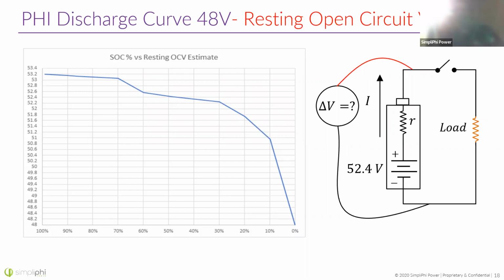This is the voltage that the battery would read if it was not powering loads, an open circuit condition. I want to make clear that the voltage of the battery bank depends on two things: state of charge, and to a small degree temperature, but mostly state of charge, as well as internal voltage drop due to internal resistance. So if you're discharging or charging the battery, the voltage will appear different than in a resting condition.